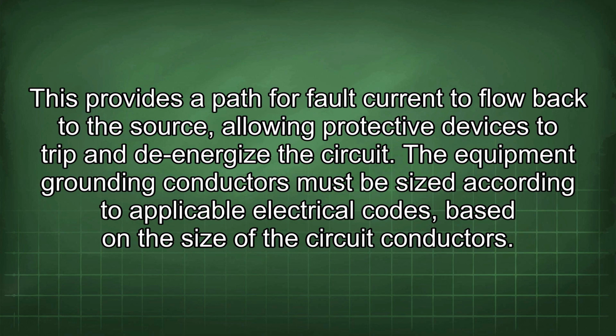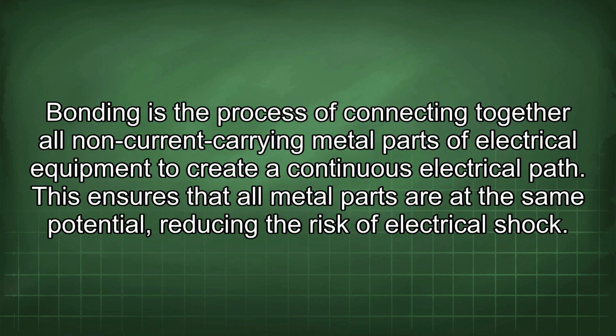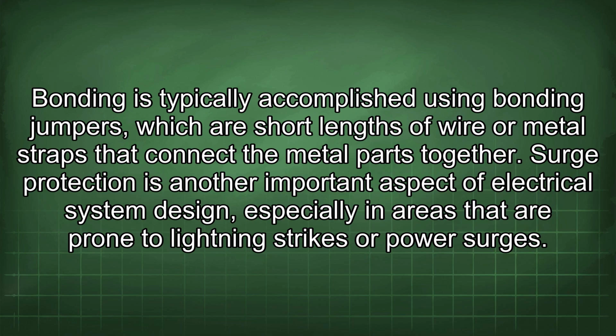Bonding is the process of connecting together all non-current carrying metal parts of electrical equipment to create a continuous electrical path. This ensures that all metal parts are at the same potential, reducing the risk of electrical shock. Bonding is typically accomplished using bonding jumpers, which are short lengths of wire or metal straps that connect the metal parts together.